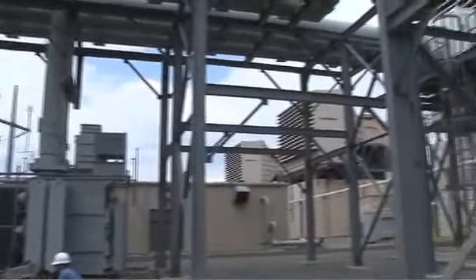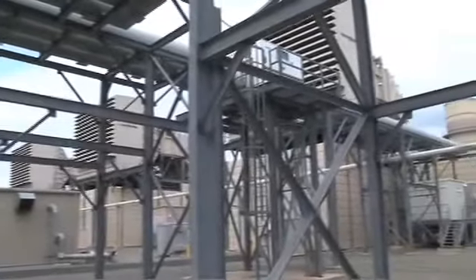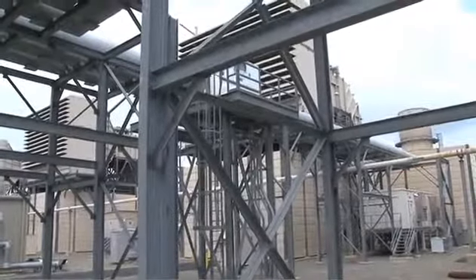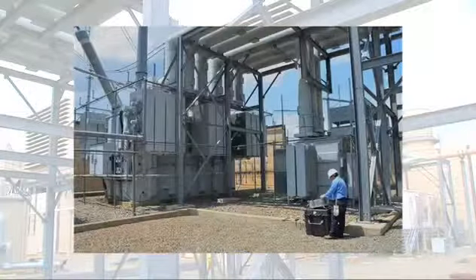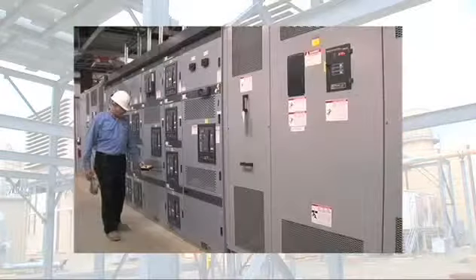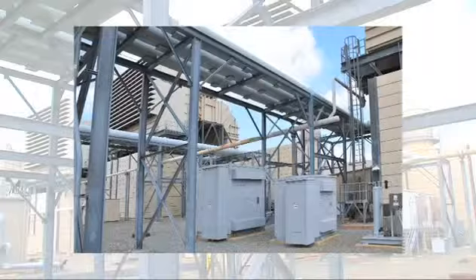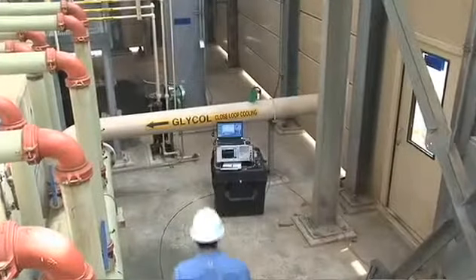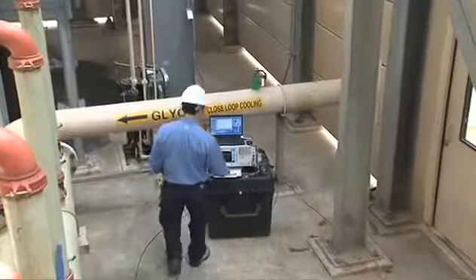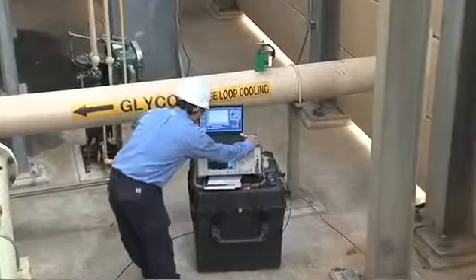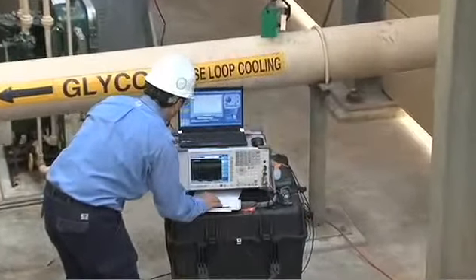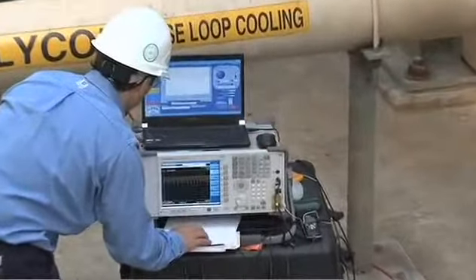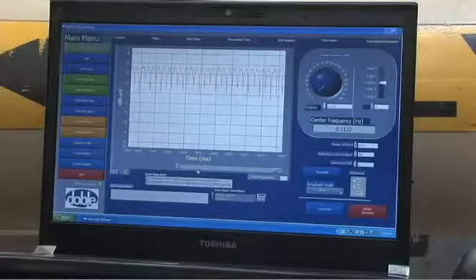It can detect a wide variety of electrical and mechanical system component problems in generators, motors, transformers, isophase bus, cables, switchgear, associated electrical system components.